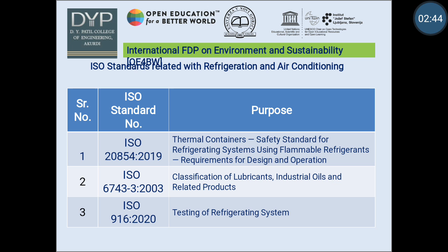Now, total there are 29 ISO standard related with refrigeration process. Here I am going to discuss 3 ISO standard. First ISO standard is ISO 20854 2019. The purpose is thermal container regarding safety standard for refrigerating systems using flammable refrigerant and requirement for design and operation. Second ISO standard is 6743-3:2003. The purpose is classification of lubricant, industrial oil, and related products regarding air compressor, refrigerant compressor. Third ISO standard is ISO 916 2020. It is related with testing of refrigerating system.